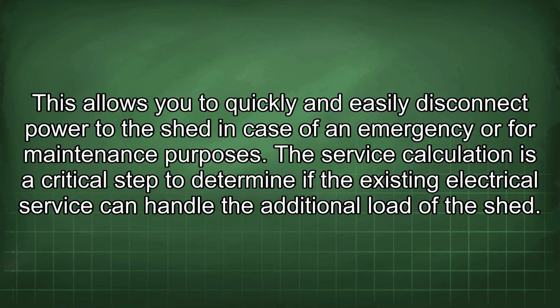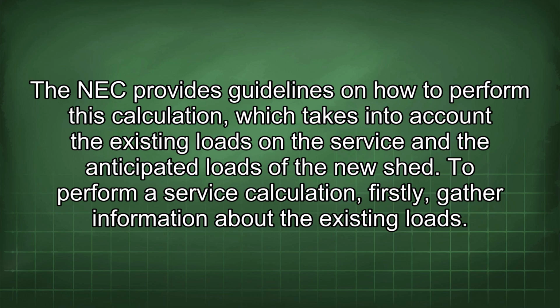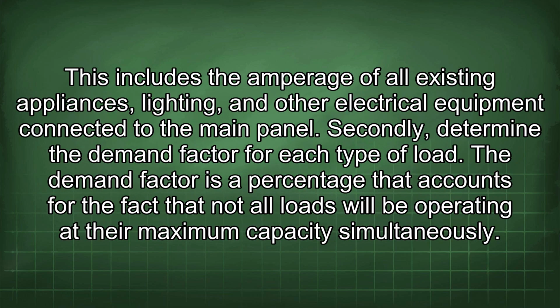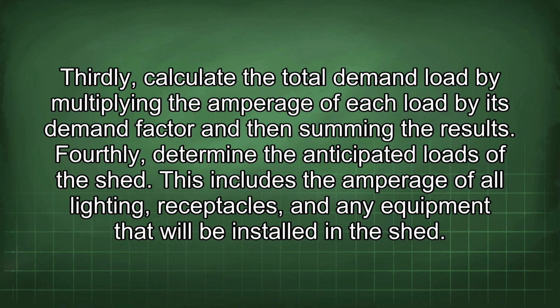The service calculation is a critical step to determine if the existing electrical service can handle the additional load of the shed. The NEC provides guidelines on how to perform this calculation, which takes into account the existing loads in the service and the anticipated loads of the new shed. To perform a service calculation, firstly, gather information about the existing loads. This includes the amperage of all existing appliances, lighting, and other electrical equipment connected to the main panel. Secondly, determine the demand factor for each type of load. The demand factor is a percentage that accounts for the fact that not all loads will be operating at their maximum capacity simultaneously. Thirdly, calculate the total demand load by multiplying the amperage of each load by its demand factor and then summing the results.